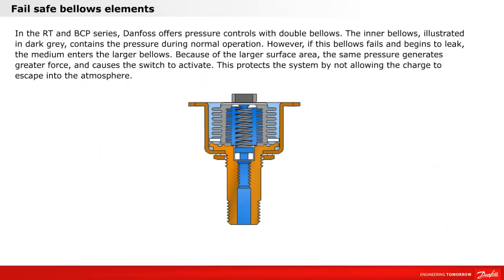In the RT and BCP series, Danfoss offers pressure controls with double bellows. The inner bellows, illustrated in dark gray, contains the pressure during normal operation. However, if this bellows fails and begins to leak, the medium enters the larger bellows. Because of the larger surface area, the same pressure generates greater force and causes the switch to activate, protecting the system by not allowing the charge to escape into the atmosphere.